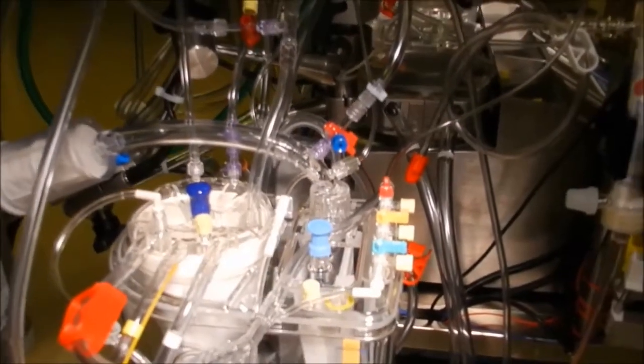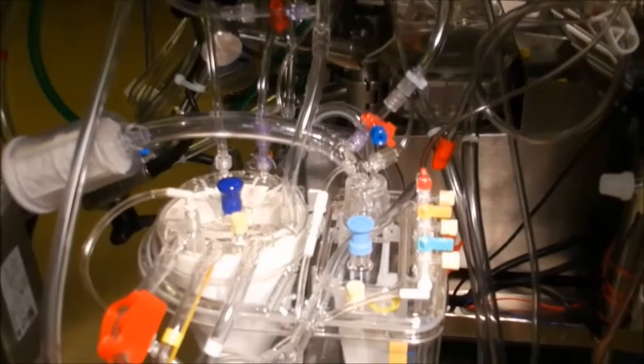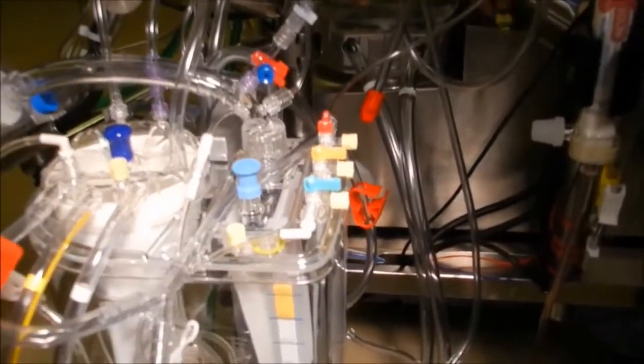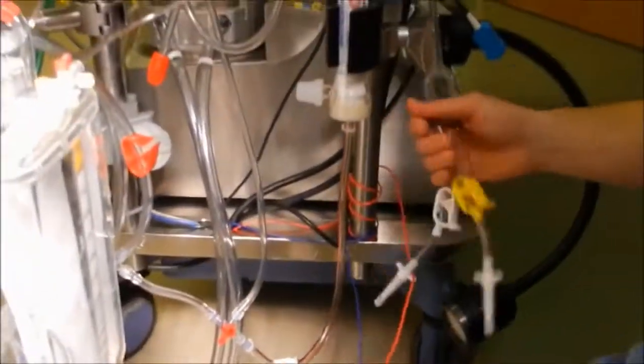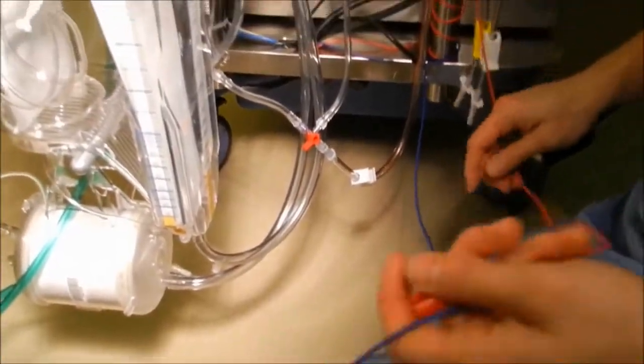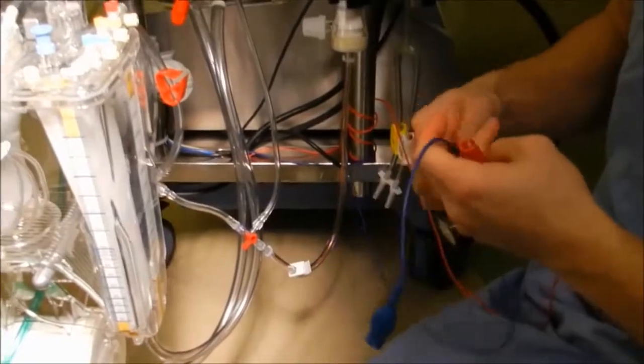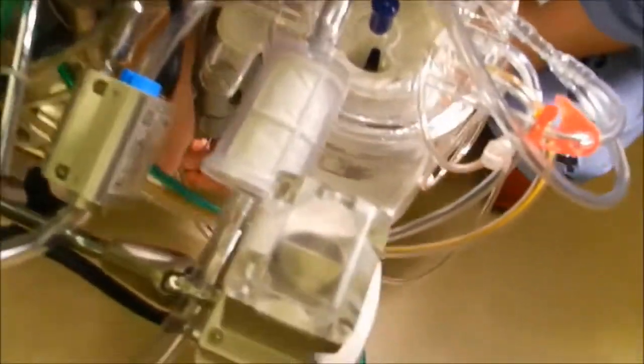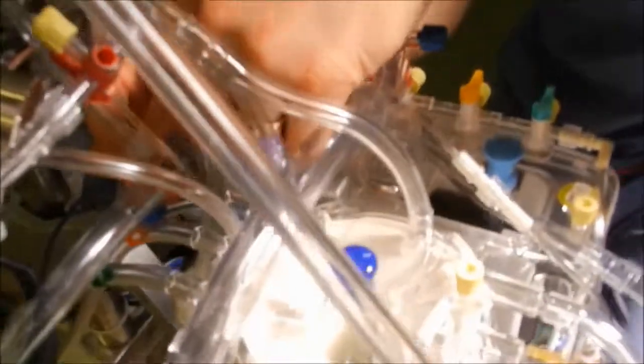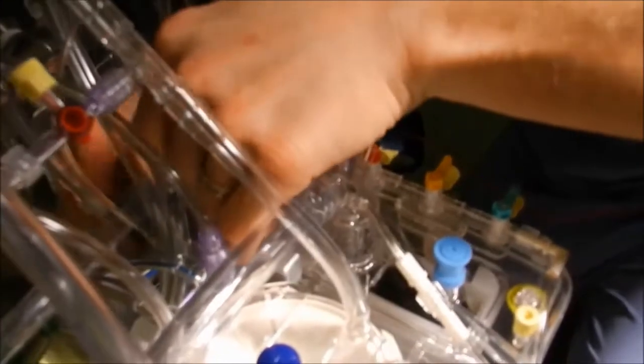Next we have to connect our ancillary devices, like our temperature management and our safety level detector. I set these up last so they don't interfere with all of your other connections or make them not sterile, because they're kind of flimsy and tend to get in the way. So obviously on the venous inlet, you can measure patient temperature coming back to you, and you want to measure your arterial outlet temperature in case you have to cool for circ arrest or warm, or things like that.